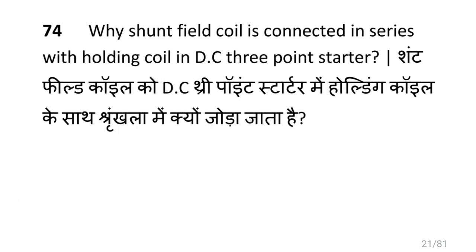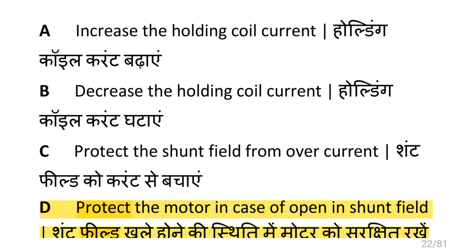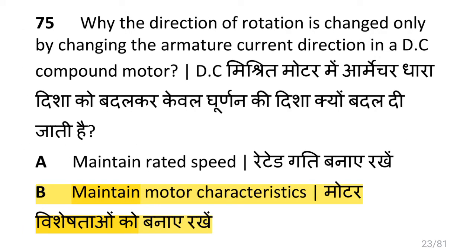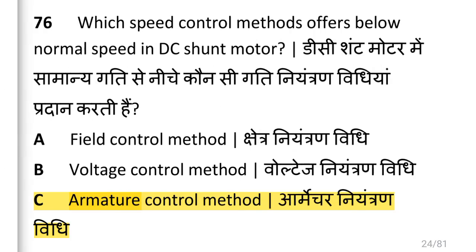Why is the shunt field coil connected in series with holding coil in DC three point starter? That is to protect the motor in case of open in shunt field. Why is the direction of rotation changed only by changing the armature current direction in a DC compound motor? Because it is necessary to maintain the motor characteristics.